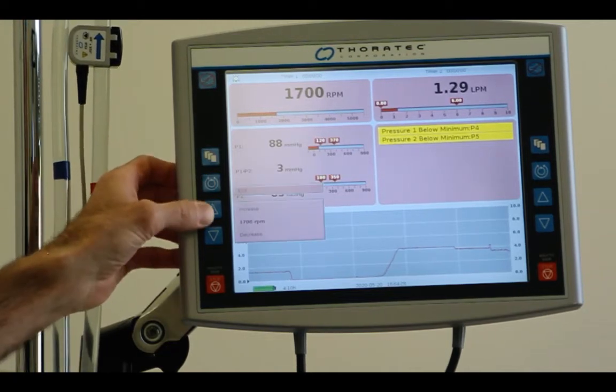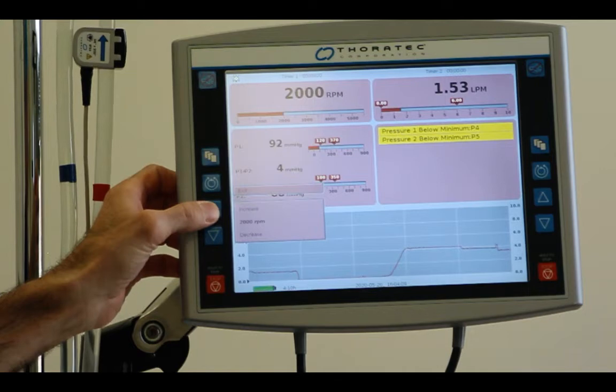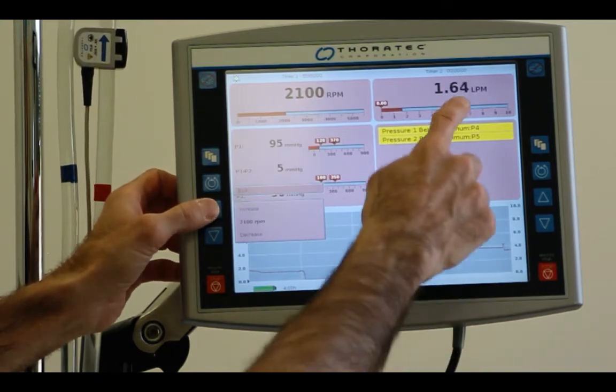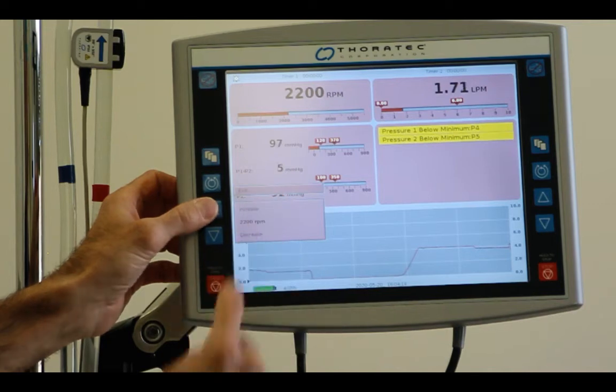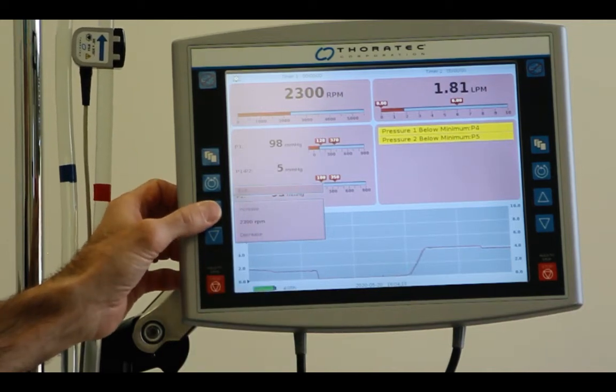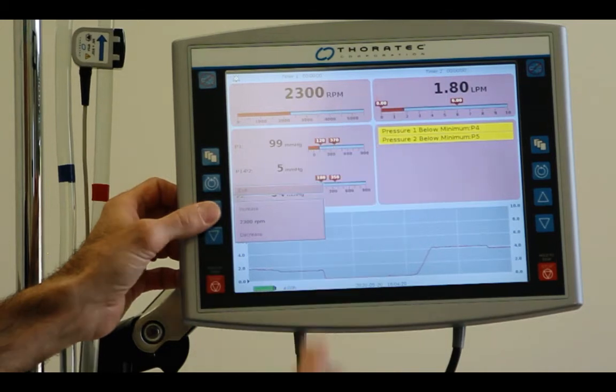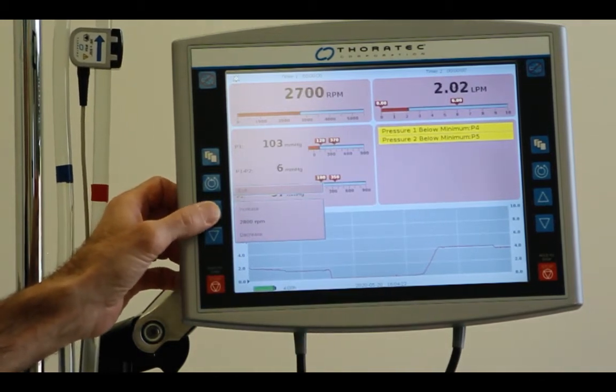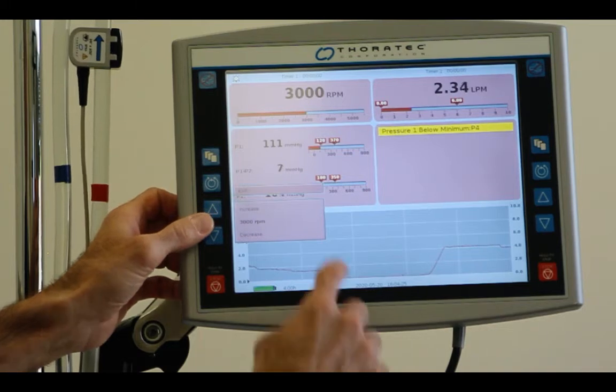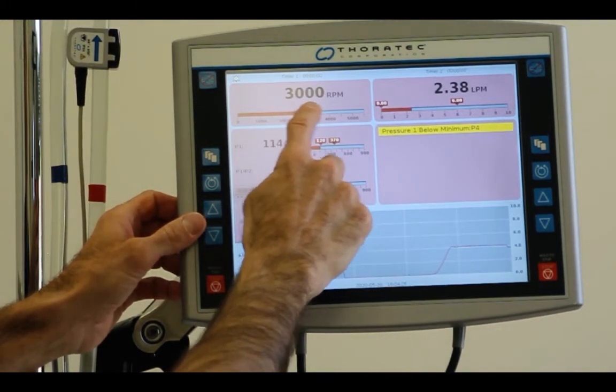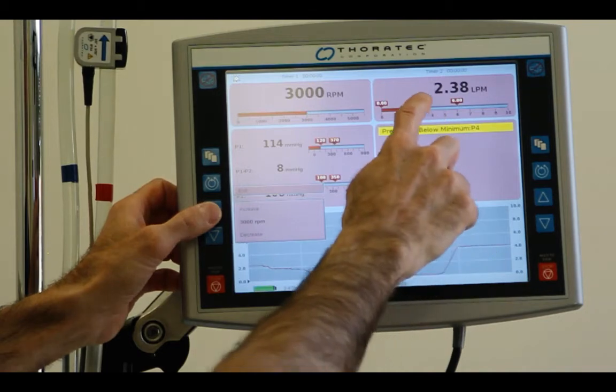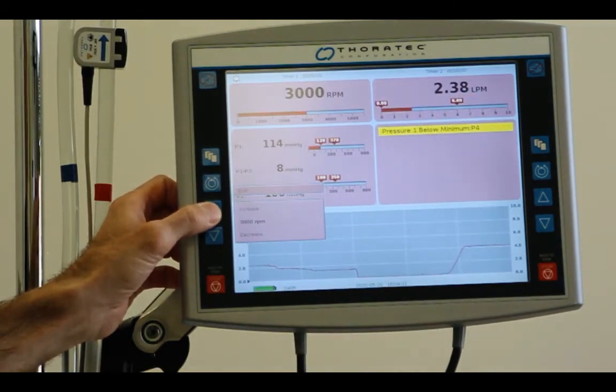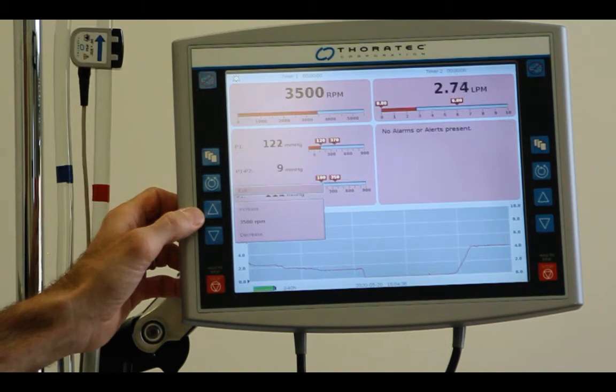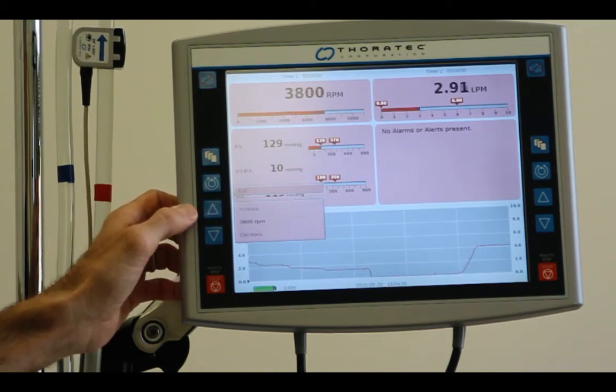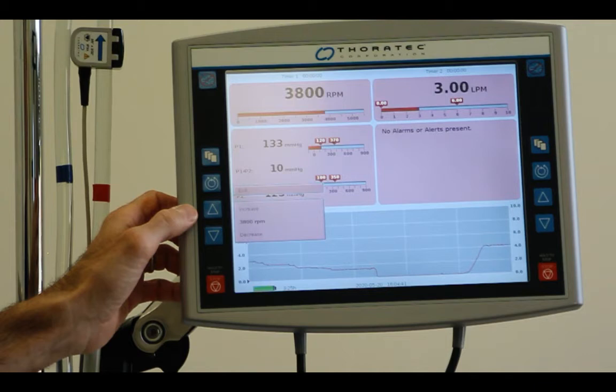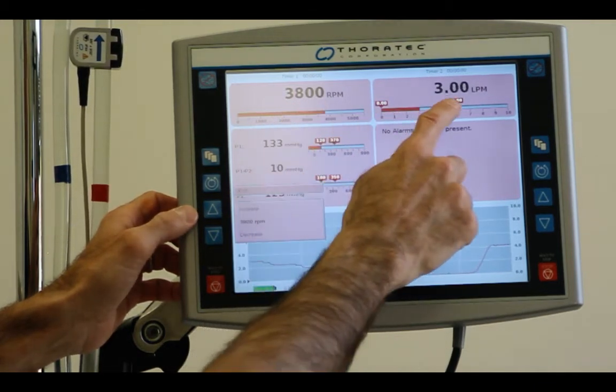And we're going to start increasing our flow until we hit one of those 3 stop points. Either we hit our top flow, or we hit a line pressure of 300. And if it is 300, then we're going to look back and try to figure out whether it's preload or afterload. So we're increasing. Wow. Our RPMs are 3,000. Our liters per minute are 2.3, 2.4. Let's say we're not really confident about this. So let's keep going. And, well, my line pressure is a lot higher.